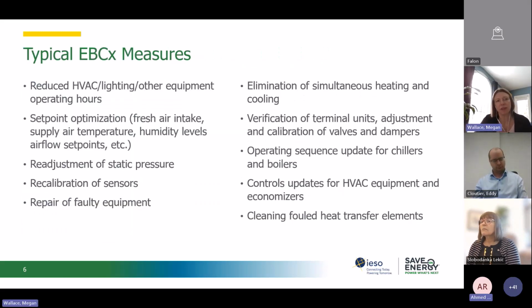So some of the typical EBCx measures that we see are reduced HVAC, lighting, and other equipment operating hours, and set point optimization for things like supply temperature, fresh air intakes, and humidity levels, readjustment of static pressure sensors, recalibration of sensors, and repair of faulty equipment. We also look at eliminating simultaneous heating and cooling, verifying terminal units such as VAV boxes, and adjusting and calibrating the valves and dampers related to the terminal devices. The operating sequences are updated for chillers and boilers, with controls updates for HVAC equipment and economizers, and also cleaning fouled heat transfer elements like heat exchangers.